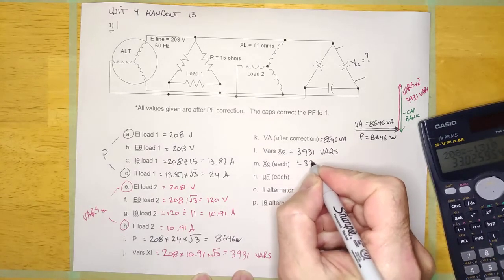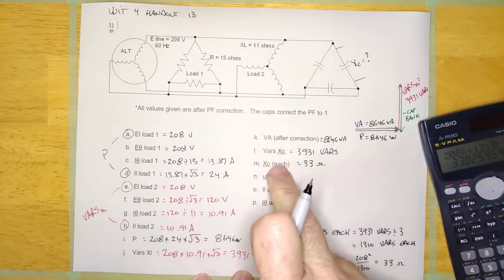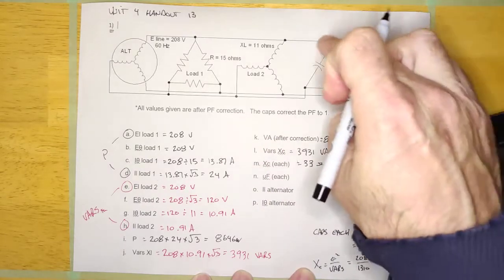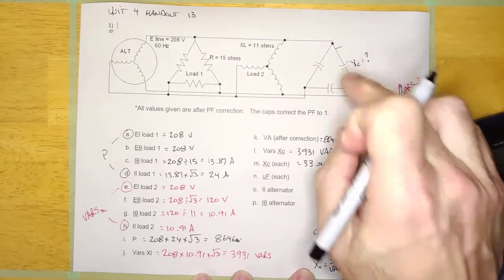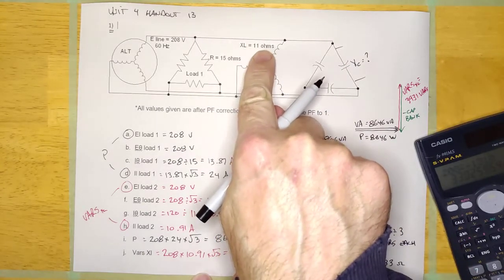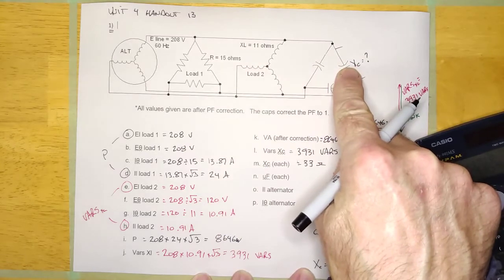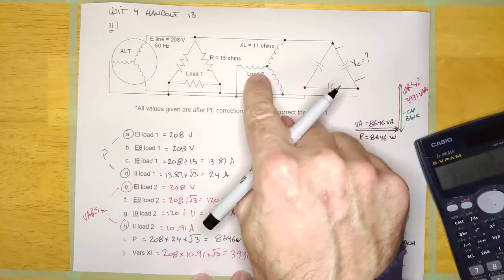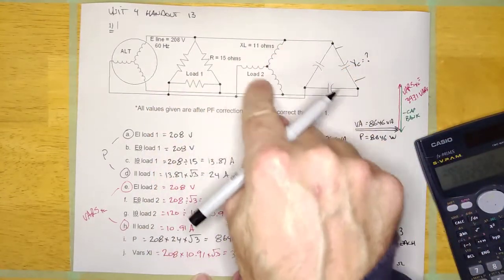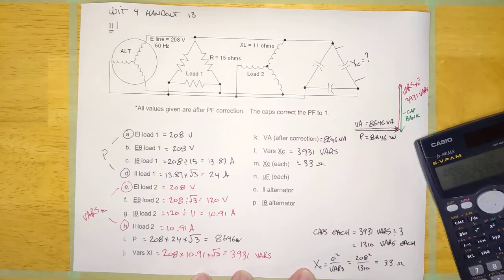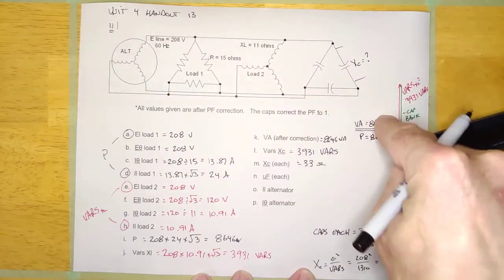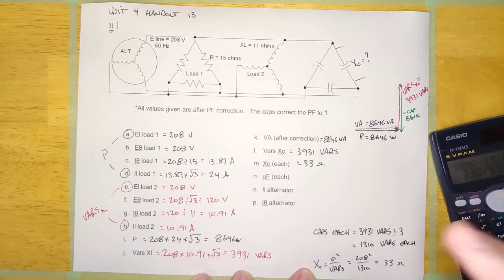208 squared divided by 1,310 equals 33 ohms. Be careful — even though the inductor is 11 ohms, the capacitor is not going to be 11 ohms, because this is not a series circuit. Also the capacitor bank is connected delta. The only proper way to solve this is with power phasors — don't take shortcuts, it won't work.